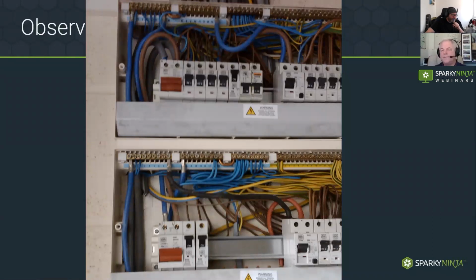Everything goes off. Broken neutral, switch neutral. Yeah, good. Yeah, so you have to really stare at this to kind of understand. So the system, this board here, this top board, is going to shut off when this goes off. This board here, every circuit is going to go off because this switching operation has obviously disconnected this neutral feeding the bar, which feeds this board down here. So we're going to single pole switch neutral when we switch this bar off. This whole board up here will go off.